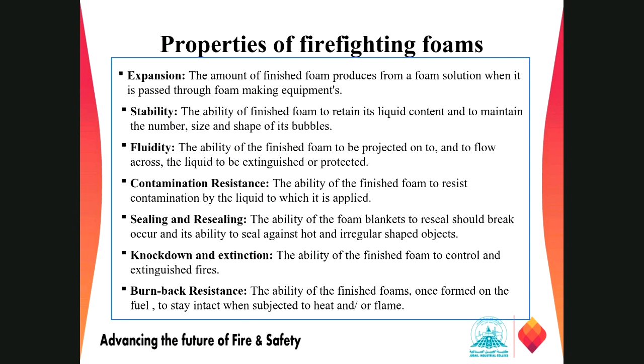The knockdown and extinction means the ability of foam to control and extinguish the fire, and the last, the burn back resistance. It is the ability of finished foam, once formed on the fuel, to stay intact when subjected to heat or flame. It means it is not getting damaged by heat or flame once discharged to the surface, and hence cooling the surface. The performance of the firefighting foams can be influenced by the type of foam making equipment, the type of the concentrate used, the type of fuel and fire, the tactics of the foam application, the rate of the foam, the quality of the foam, and the length of free burn.